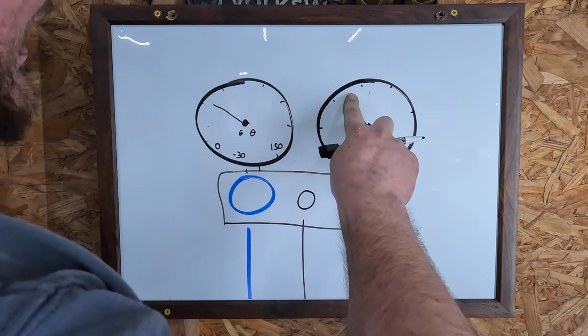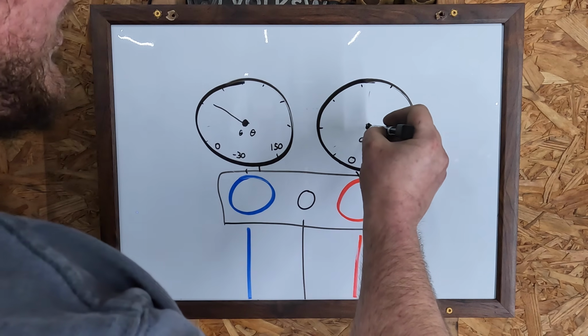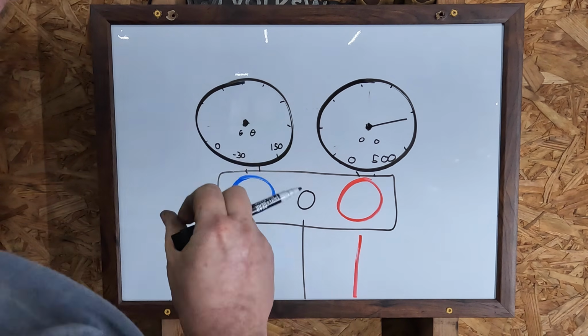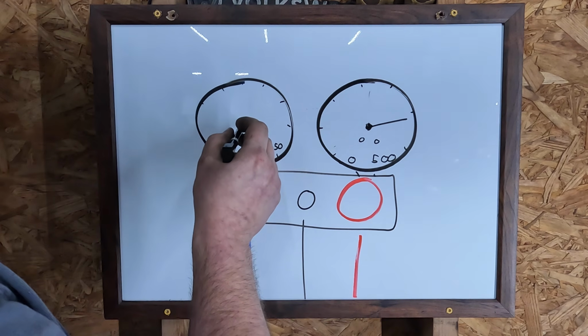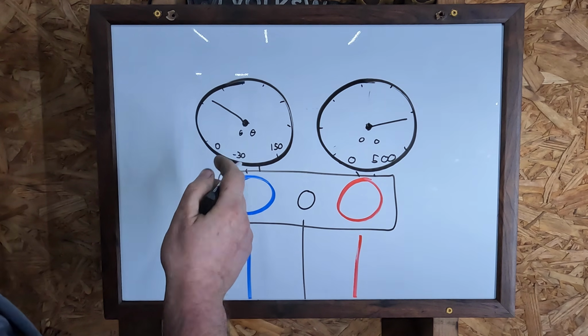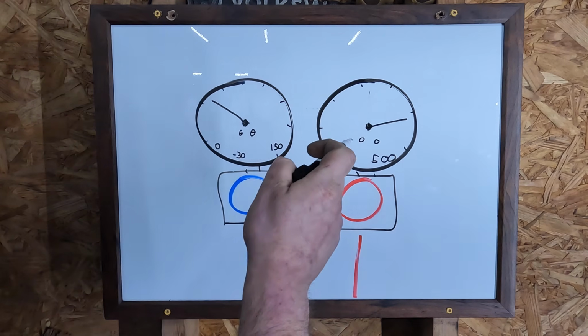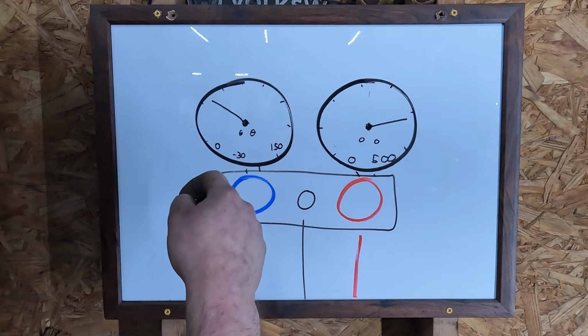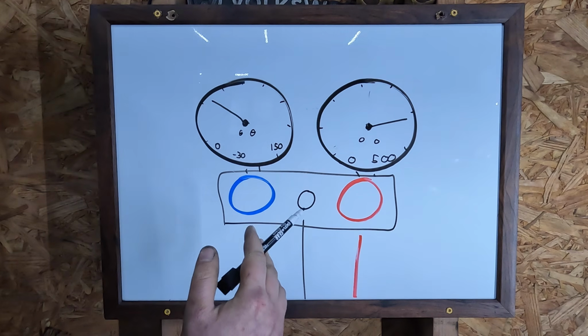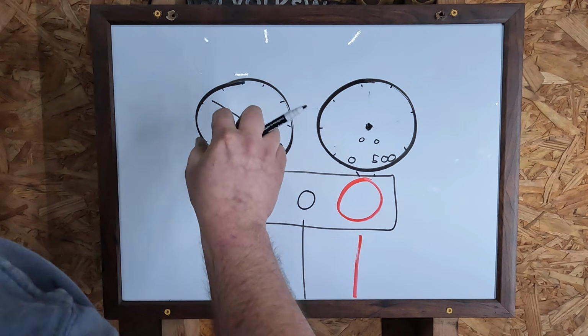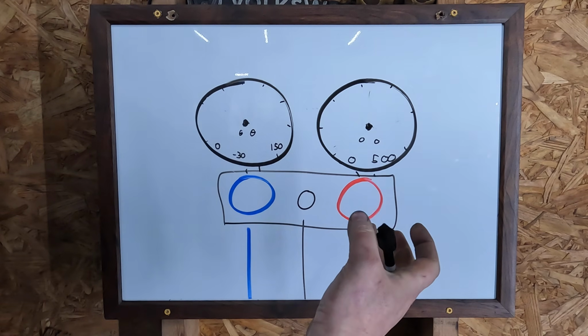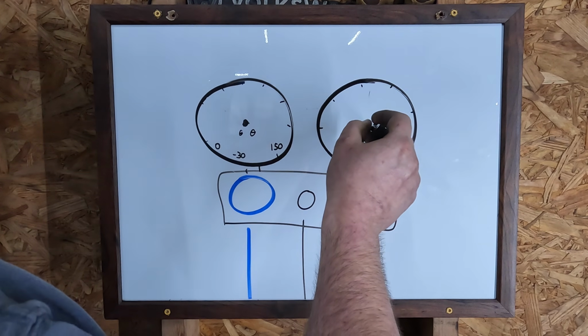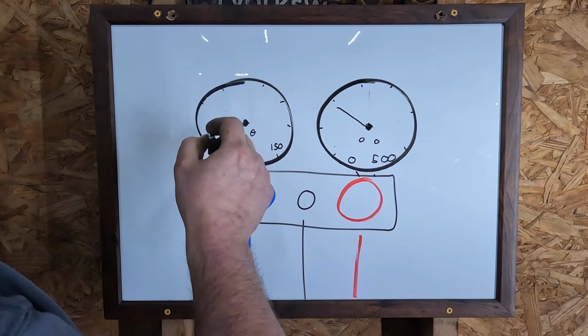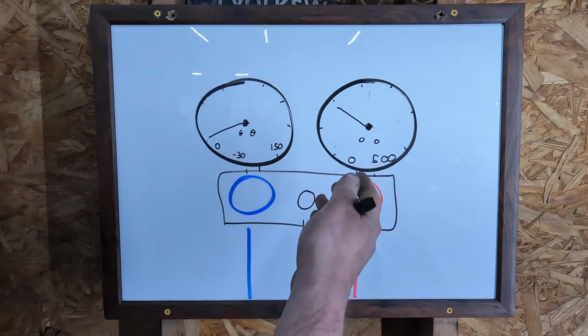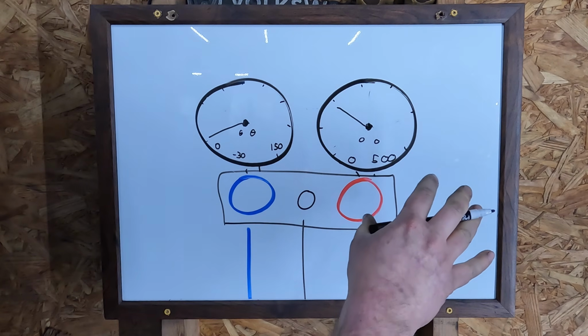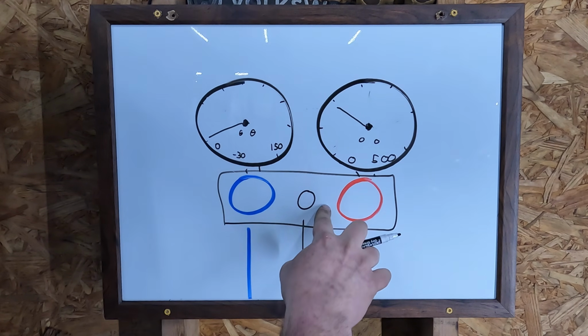Now, another issue you could have is if your discharge side is way high and your low side is not equally high, rather somewhere between normal and low, that could mean you have a restriction somewhere between the compressor outlet and the expansion valve, and there is too much resistance in the system. And finally, if you just have a low charge, the compressor isn't going to have anything to suck on. Your ratio will be roughly the same, but both sides are just going to be low. Then again, this applies to literally every type of air conditioning system, so there are many resources from actual professionals on how to troubleshoot that.